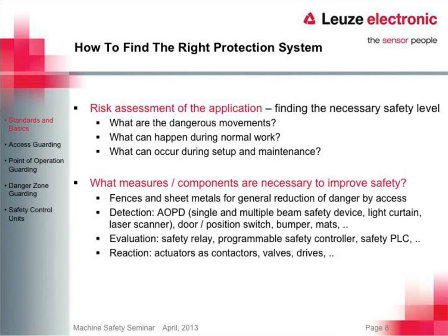We need to determine what measures and components are necessary to improve safety on the machine. Is it going to be fences and sheet metal for general reduction to keep somebody out? Or are we going to look for a detection-based solution, which would be an AOPD — an active optoelectronic protective device — typically a light curtain, multi-beam, or a safety scanner? The components that go along with that include a safety relay or safety controller, actuators, and contactors for the valves and drives. There's a lot that goes into the safety-related portion of the control system.